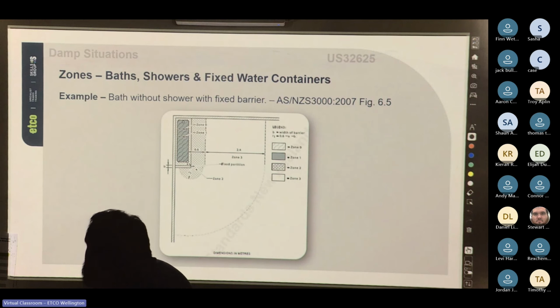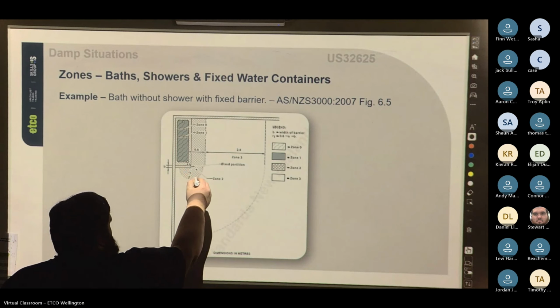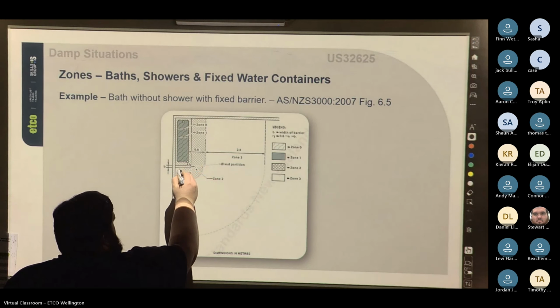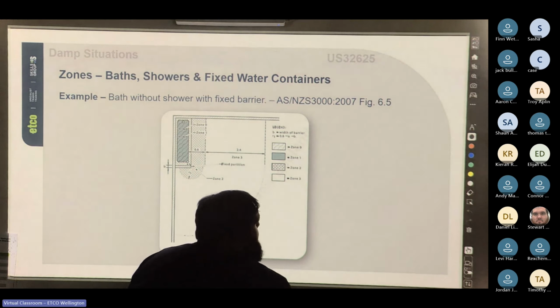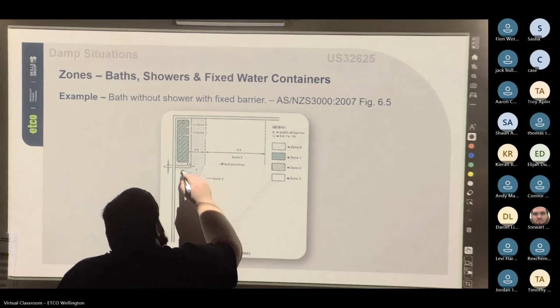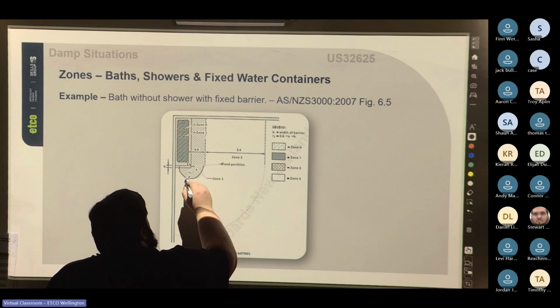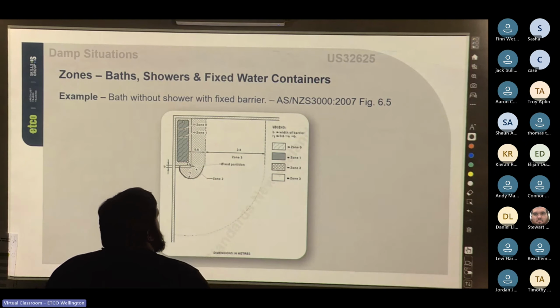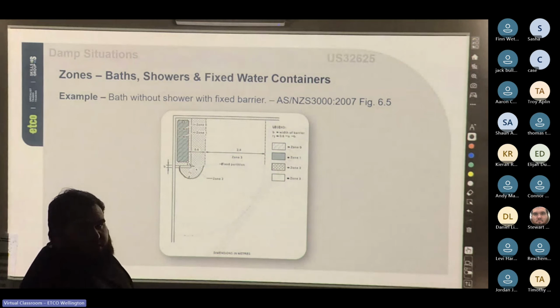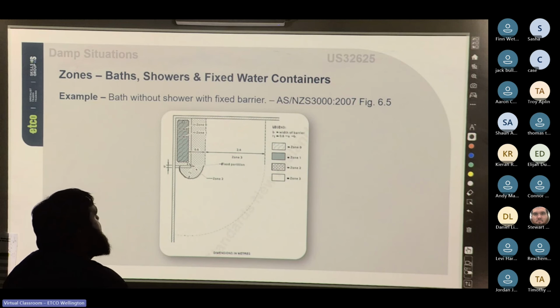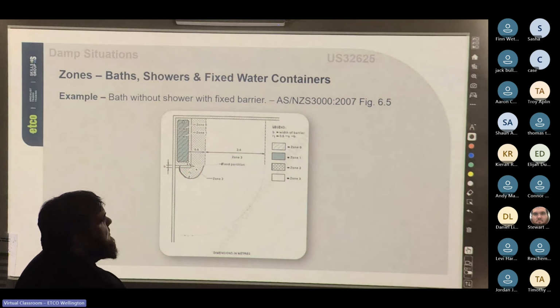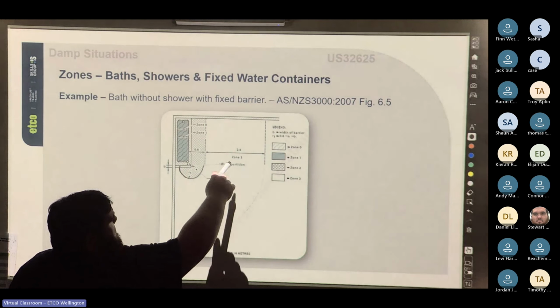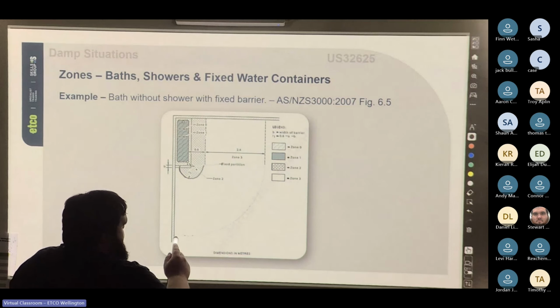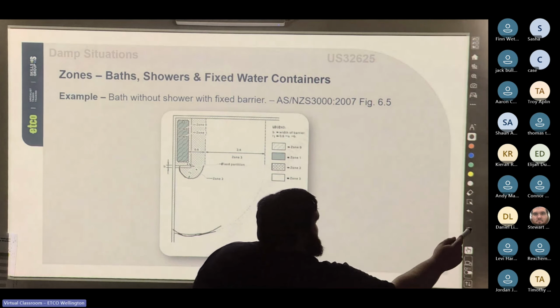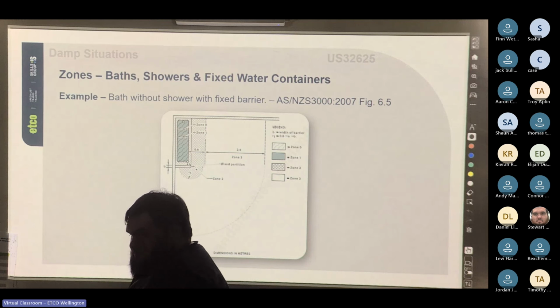there is a kind of curve here because it gets to this partition here, and then it curves around in a circle on that point. So it uses the end of the partition wall as the pivot point for the zone, and that's where zone 2 ends. And then, of course, zone 3 is 2.4 meters out from that, and there is that slight back curvature down the bottom here as well. So that's what happens if you have a fixed barrier on your bathtub.